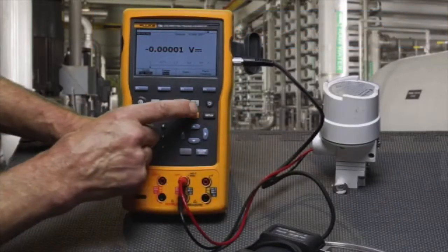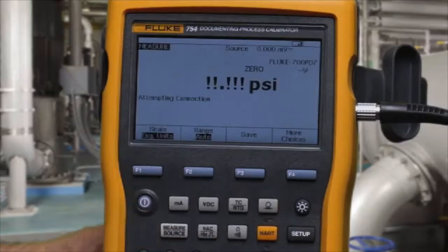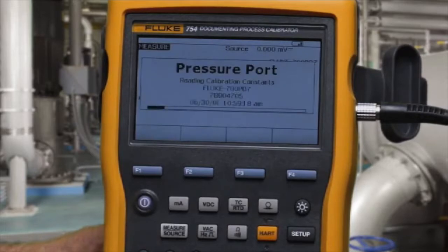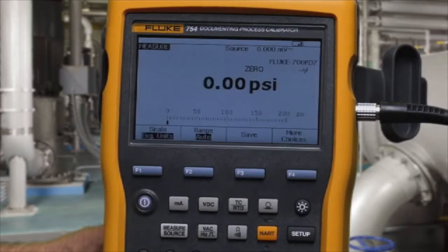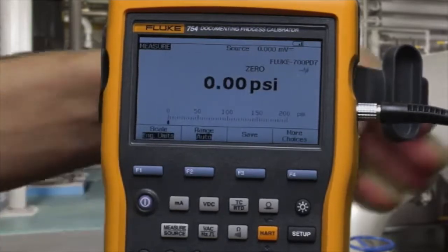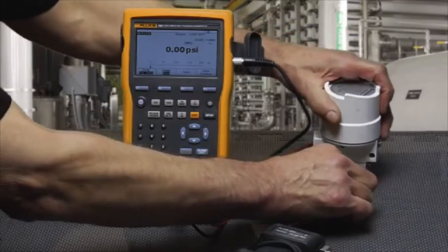We make our connections, select measure pressure. The calibrator finds the pressure module, and we press clear 0 to make sure we have a good 0. Connect the pressure module to the output of the I2P.